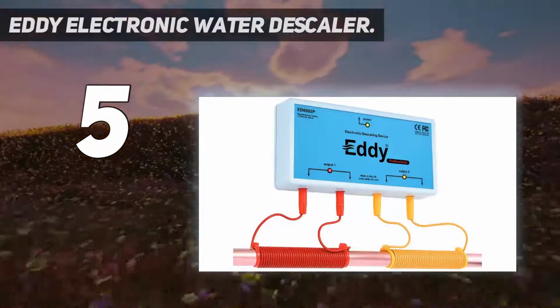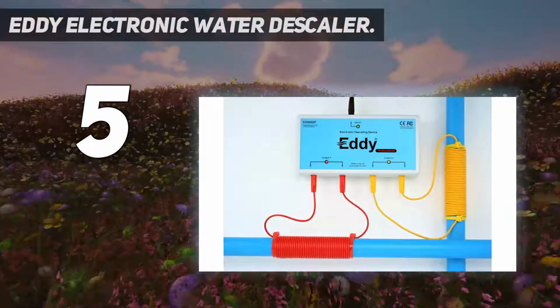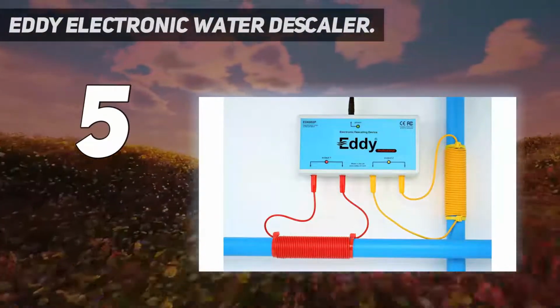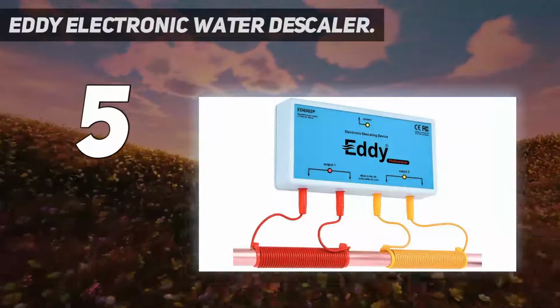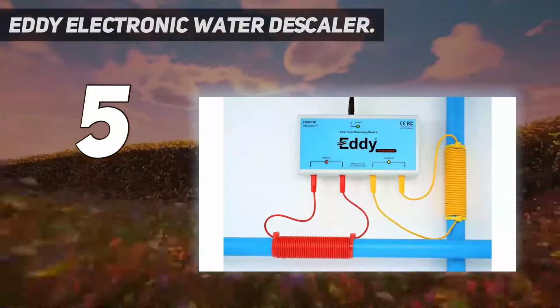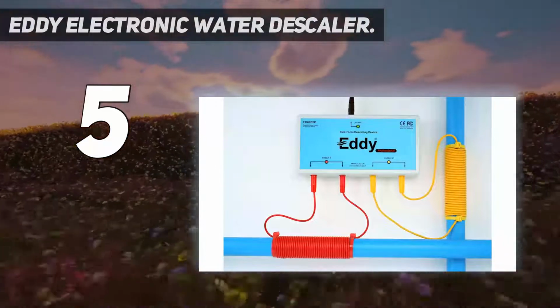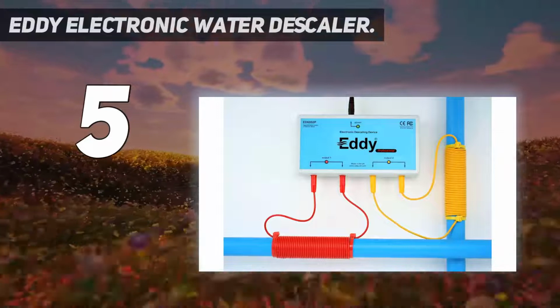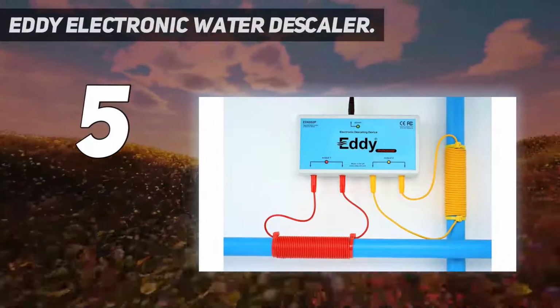Once the compounds have been removed, you can send the water through the system as you normally would. This particular system can treat up to 50 grains per gallon of hard water. That means it can handle some pretty hard water. Keep in mind this particular system does not remove calcium or magnesium from the water supply. It works by crystallizing those 2 minerals and turning them into stable forms so they won't bind to surfaces and cause soap to be ineffective.